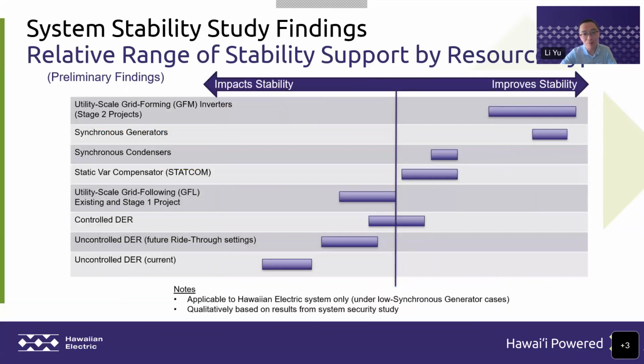This slide basically summarizes what we see from our system stability study, from only this perspective, and for our system, how we categorize all those grid resources, how they contribute to system stability. We do believe that with good short-term or current capability and tuned control, the GFM stage 2 projects can provide really good performance for our system stability to mitigate all those risks we see in our system. And we believe synchronous condensers can do so, but the only reason that we put GFM more toward the improved stability side than synchronous generators is that we believe GFM can even overcome the disadvantage of the synchronous generator swing.